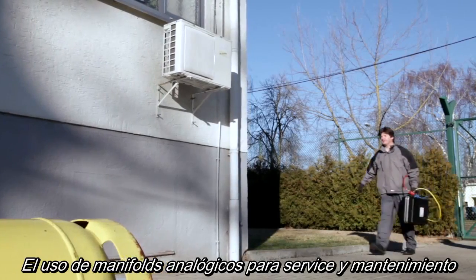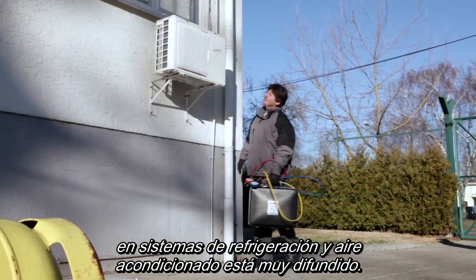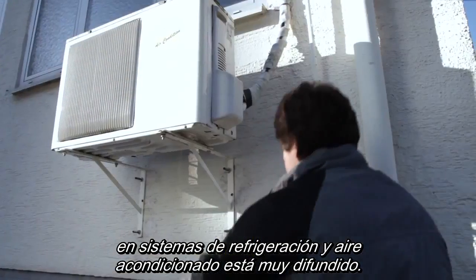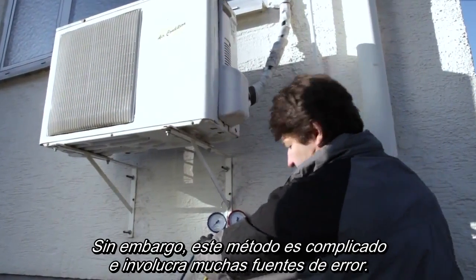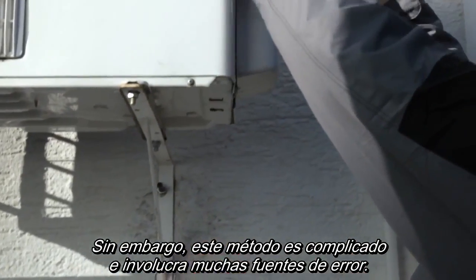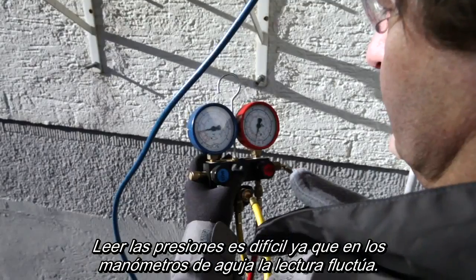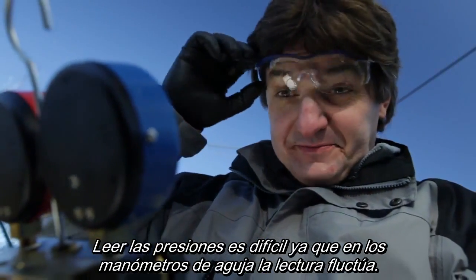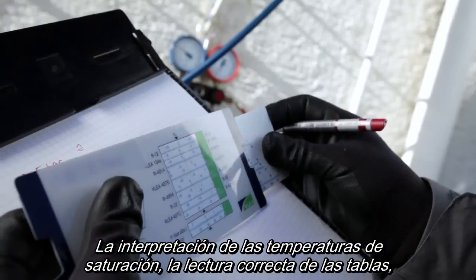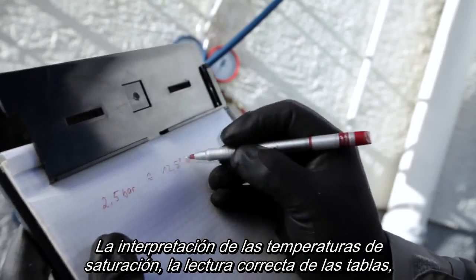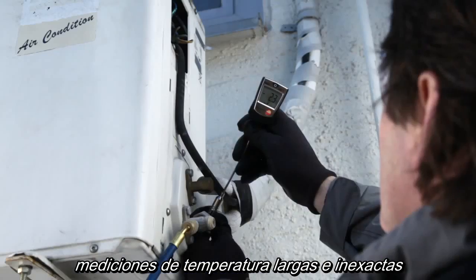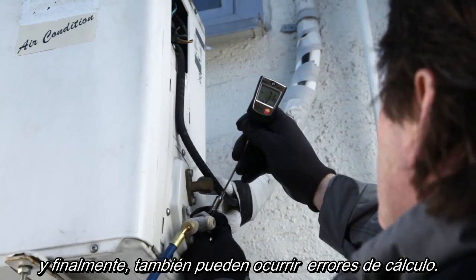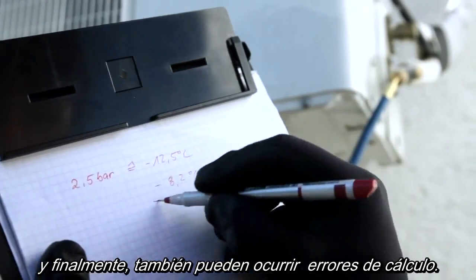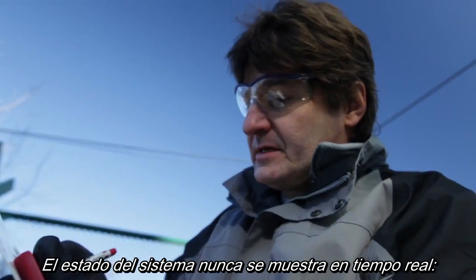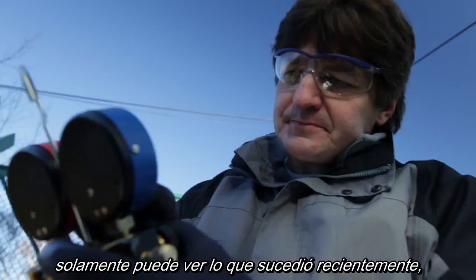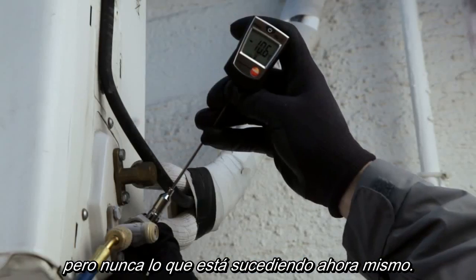The use of analog manifolds for service and maintenance of refrigeration and air conditioning systems is widespread. However, this method is complicated and involves many sources of error. Reading off the pressures is difficult since the manometer display often fluctuates. Interpretation of the saturation temperatures, exact read-off of the tables, inaccurate, time-consuming temperature measurement, and finally, calculation errors can also occur. The status of the system is never displayed in real time. You only ever see what's recently happened, never what is happening right now.